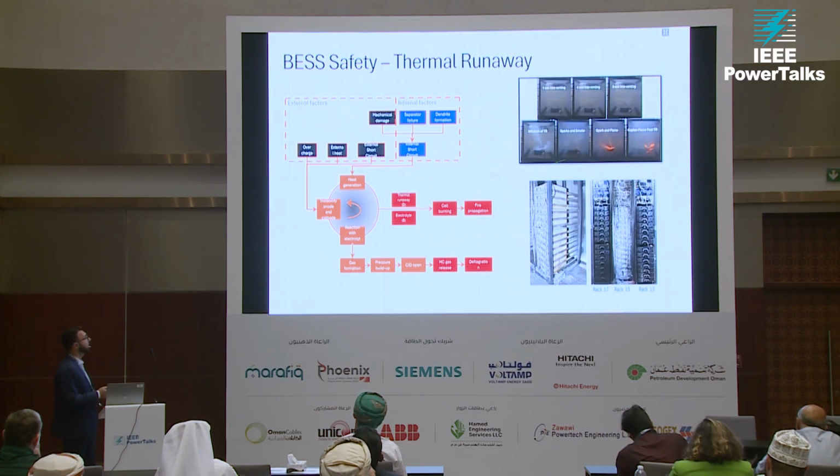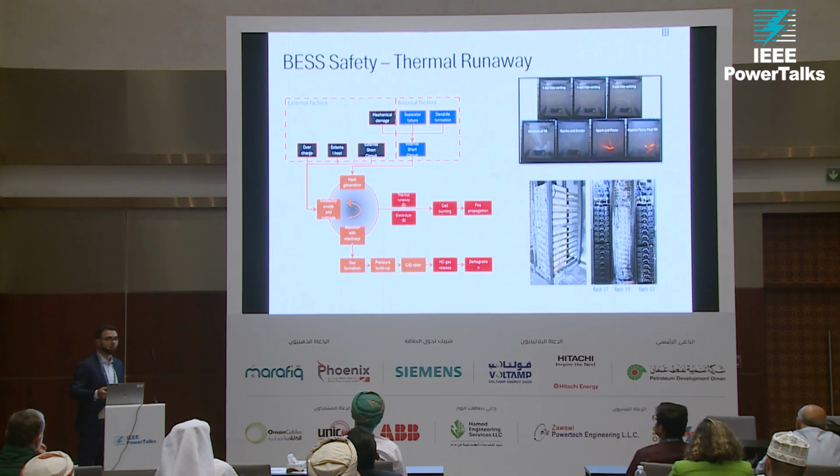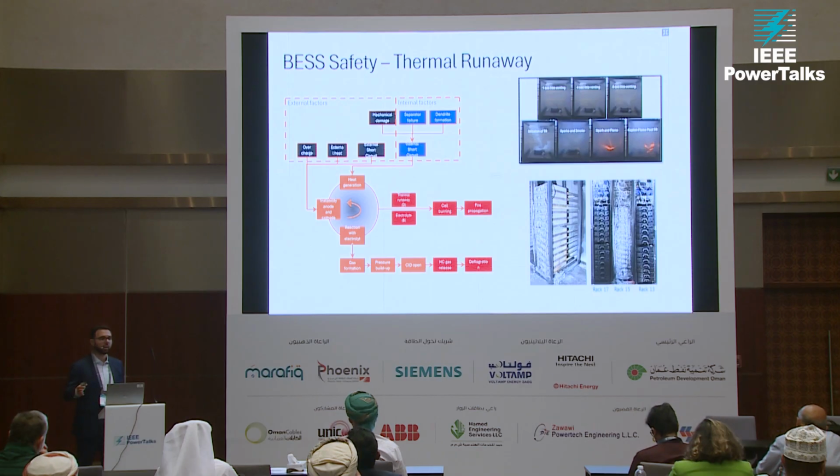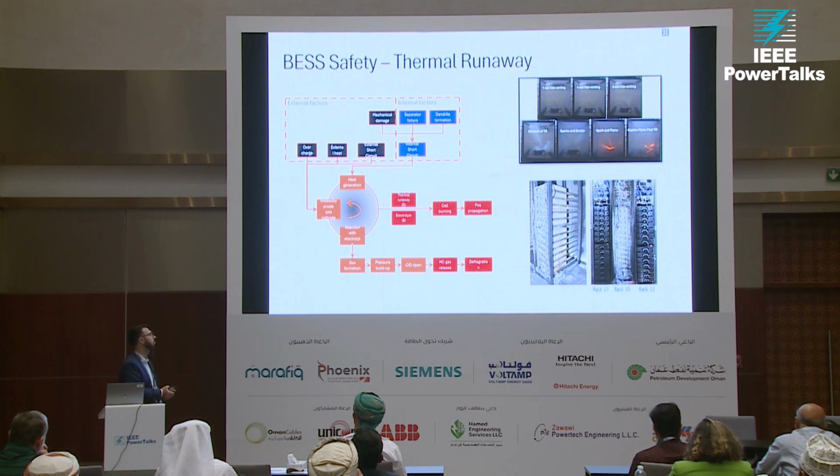So you have cell burning, then you have what's called propagation, and the industry is focusing on propagation. It's okay to have a cell fail and catch fire, but it's really bad if you have a container fail and catch fire. So we try to keep it so that when failures happen, let's just keep it contained to one small component, not expand.